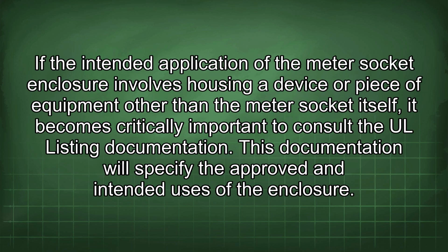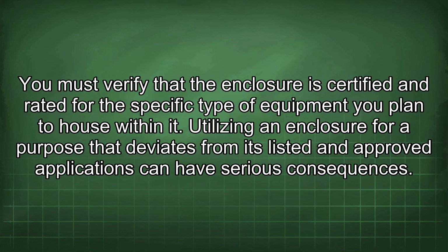If the intended application of the meter socket enclosure involves housing a device or piece of equipment other than the meter socket itself, it becomes critically important to consult the UL listing documentation. This documentation will specify the approved and intended uses of the enclosure. You must verify that the enclosure is certified and rated for the specific type of equipment you plan to house within it. Utilizing an enclosure for a purpose that deviates from its listed and approved applications can have serious consequences.